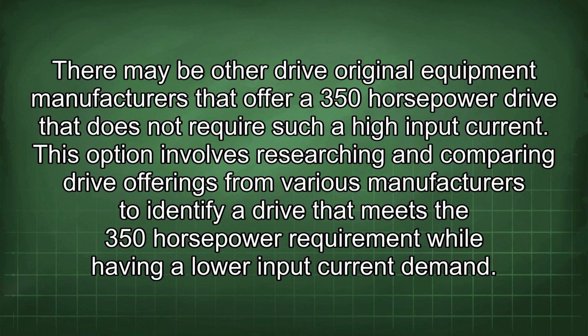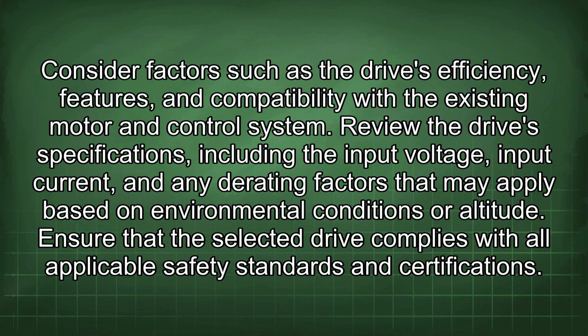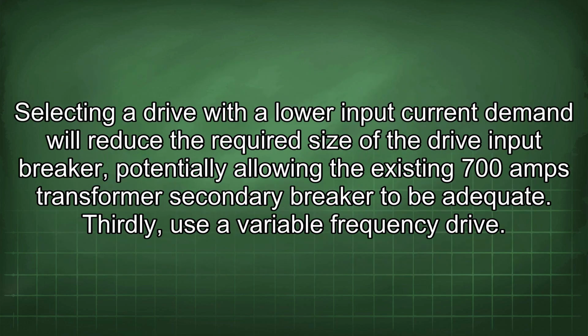high input current. This option involves researching and comparing drive offerings from various manufacturers to identify a drive that meets the 350 horsepower requirement while having a lower input current demand. Consider factors such as the drive's efficiency, features, and compatibility with the existing motor and control system. Review the drive specifications, including the input voltage, input current, and any derating factors that may apply based on environmental conditions or altitude. Ensure that the selected drive complies with all applicable safety standards and certifications. Selecting a drive with a lower input current demand will reduce the required size of the drive input breaker, potentially allowing the existing 700 amps transformer secondary breaker to be adequate.